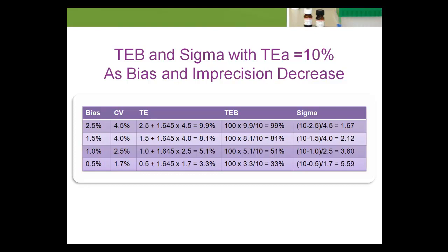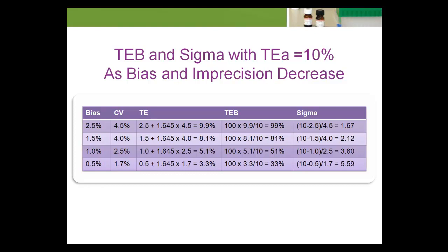In the fourth row of the table, the bias is 0.5 percent and the CV is 1.7 percent. TE equals 3.3 percent, TEB equals 33 percent, and sigma equals 5.59. A process where only a third of the TEA specification is consumed by the test system's bias and imprecision is associated with a high sigma value. Row 3 of the table suggests that for the test system to be capable of meeting the laboratory's desired quality goals — sigma values greater than or equal to 3.5 — the TEB should not exceed 50 percent. If more than 50 percent of your allowable error specification is consumed by your test system bias and imprecision, you are going to have a difficult time assuring that your reported patient results are meeting your quality goals. A lab should strive for a TEB of 33 percent or less.